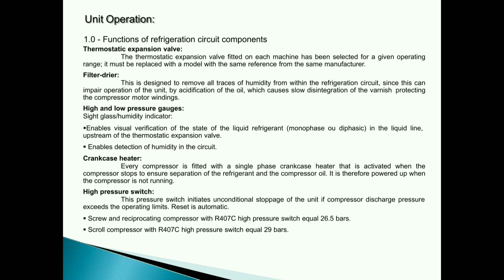High and low pressure gauges, sight glass humidity indicator. Enables visual verification of the state of the liquid refrigerant, monophase or diphasic, in the liquid line, upstream of the thermostatic expansion valve. Enables detection of humidity in the circuit. Crankcase heater. Every compressor is fitted with a single-phase crankcase heater that is activated when the compressor stops to ensure separation of the refrigerant and the compressor oil. It is therefore powered up when the compressor is not running.